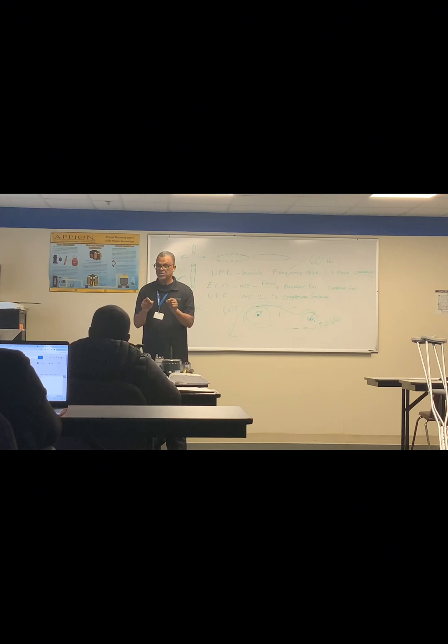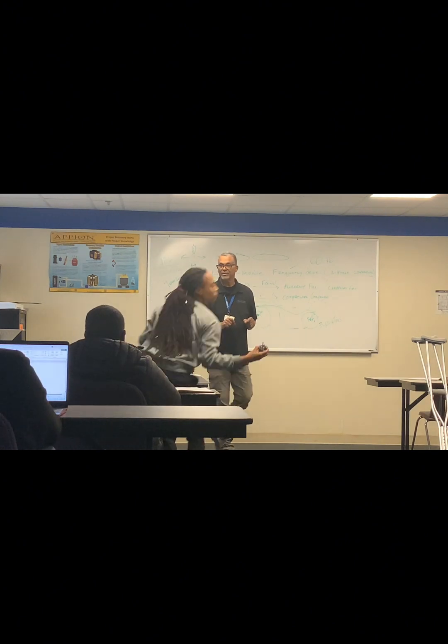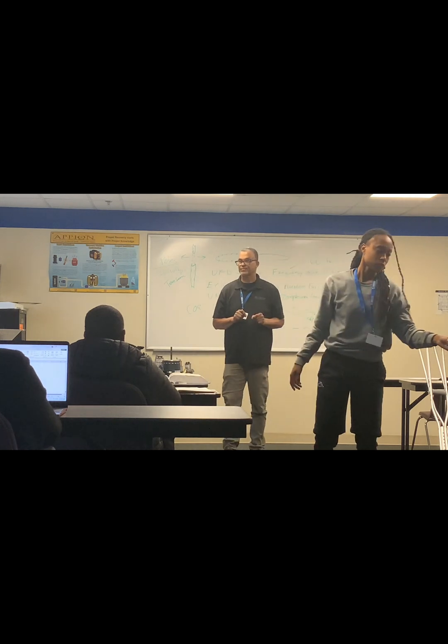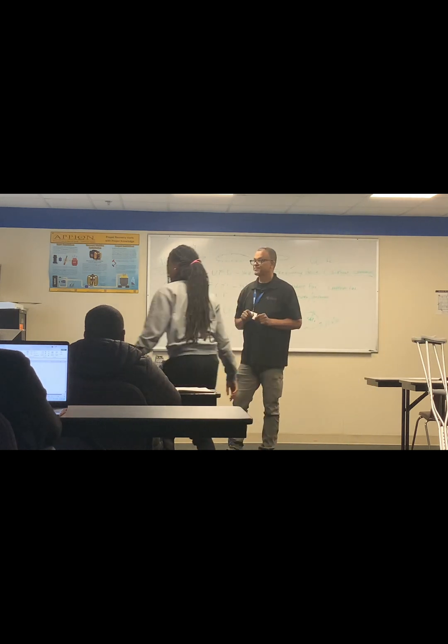You can test the terminals without power, put 24 volts to it, and see what closes. I do it all the time. That's going to be normally open. There was no power there before I applied power. When I applied 24 volts, it closed. Those are the 2 terminals I'm going to use. Normally open. Because a lot of the boards are different, so I want to use that so it's faster.